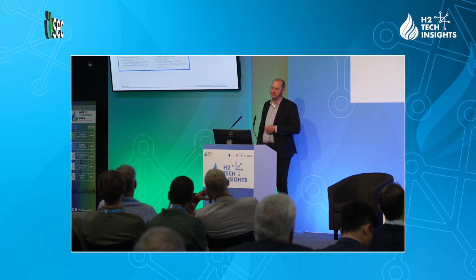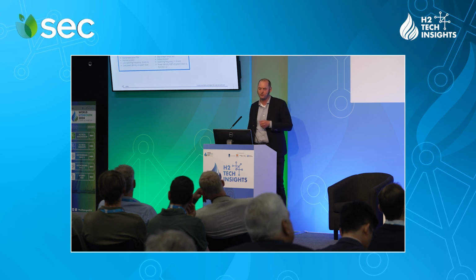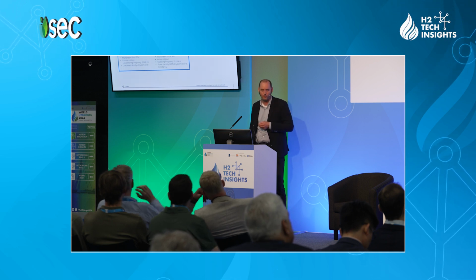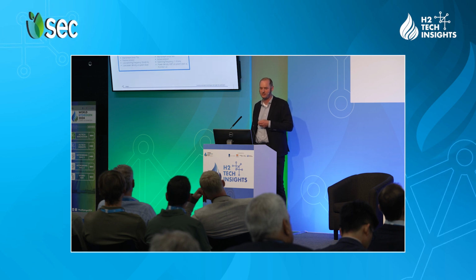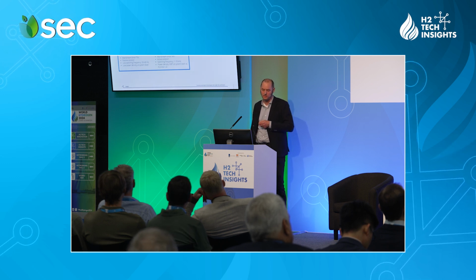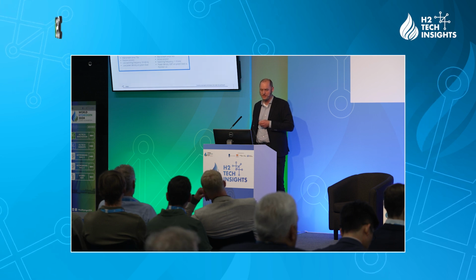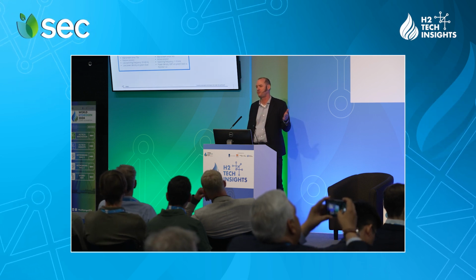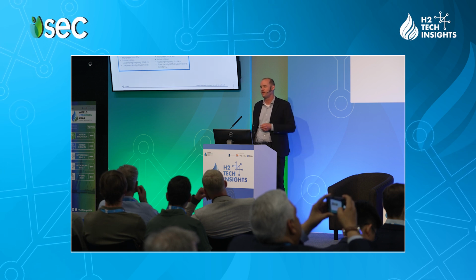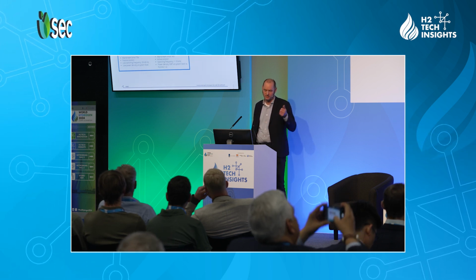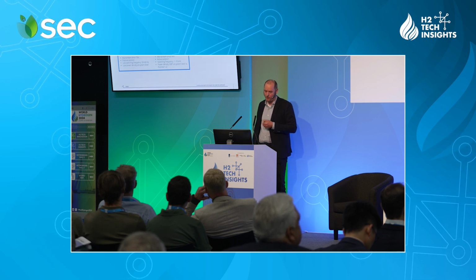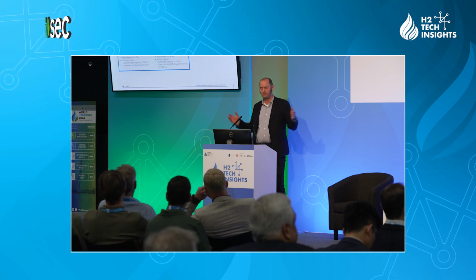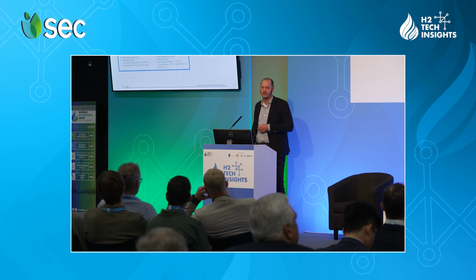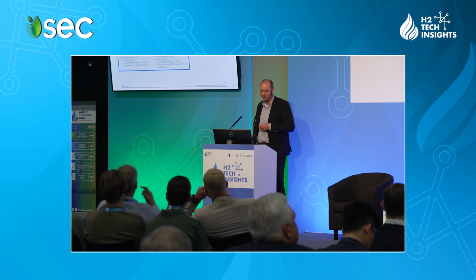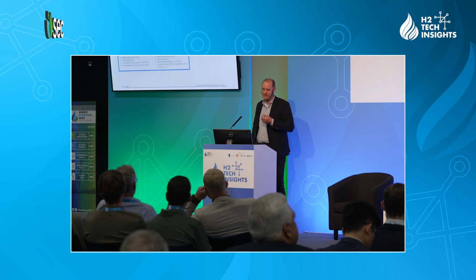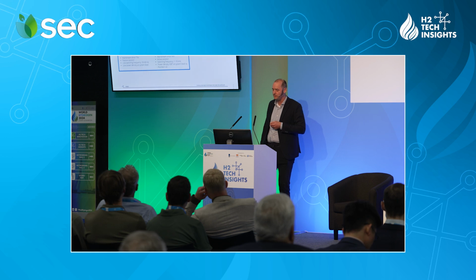So now, if you look at the semiconductor technologies that are available, there are actually three. Two of them are now incumbent. Something that's been used since the 70s, a very old technology, is thyristor-based technology. It's a passive solution. It basically switches more or less at the same frequency as the grid. So whatever happens on the grid, you can't do a whole lot but dissipate energy. And the power density at system level, if you take into account all the filters that you need to apply to have this nice sinusoidal waveform, is pretty poor.